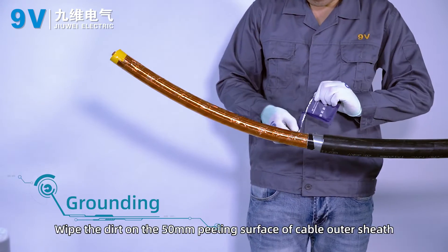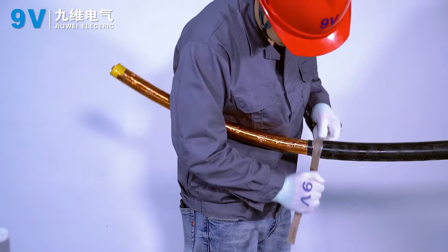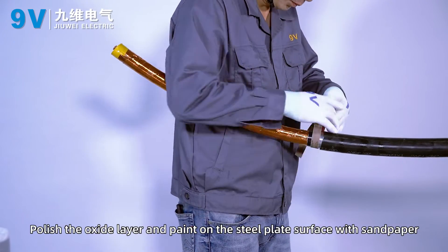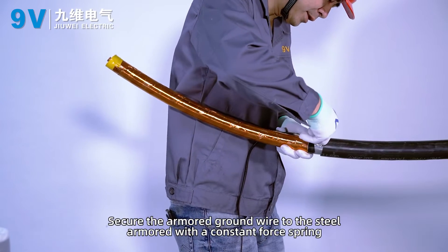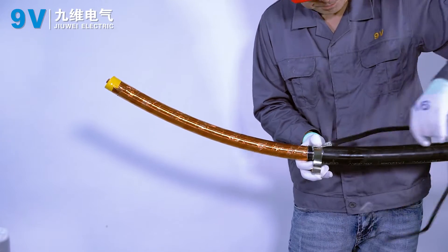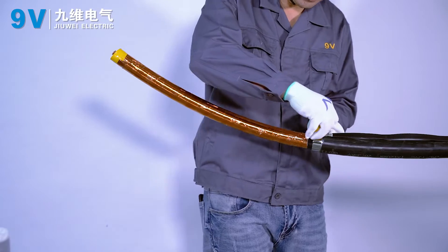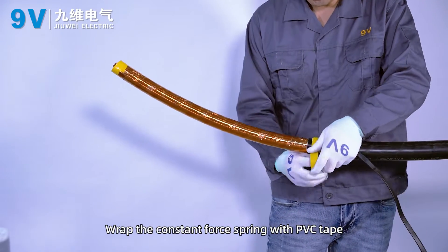Grounding. Wipe the dirt on the 50 mm peeling surface of the cable outer sheath. Polish the oxide layer and paint on the steel plate surface with sandpaper. Secure the armoured ground wire to the steel armour with a constant force spring. Wrap the constant force spring with PVC tape.